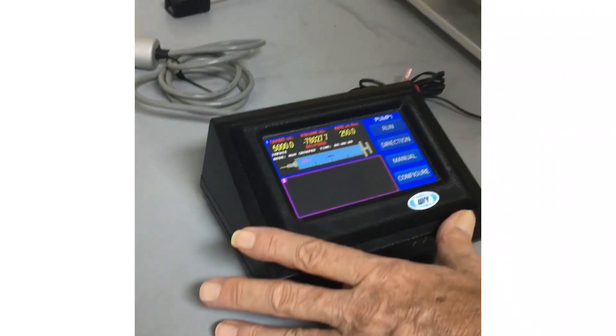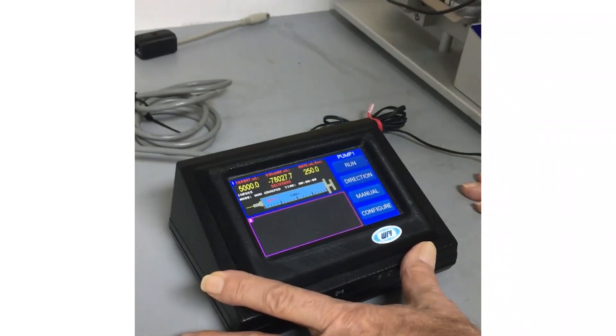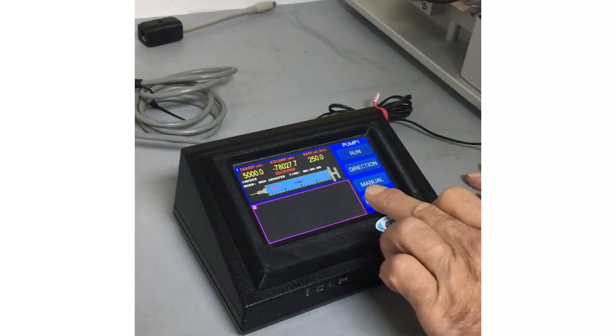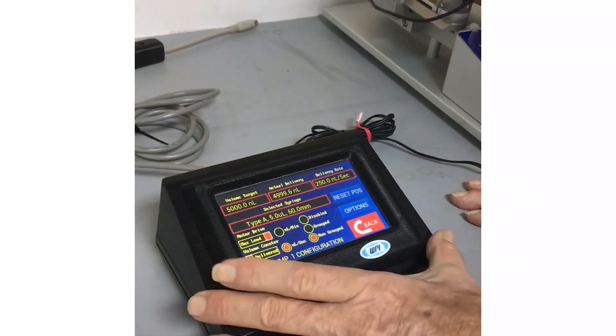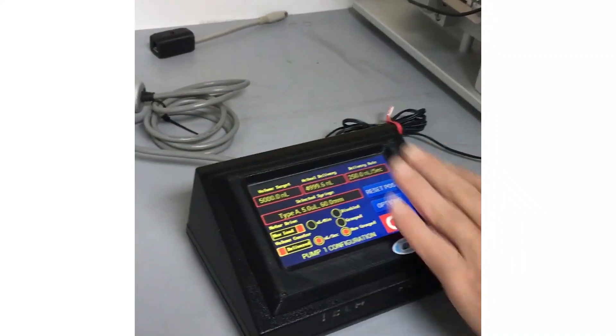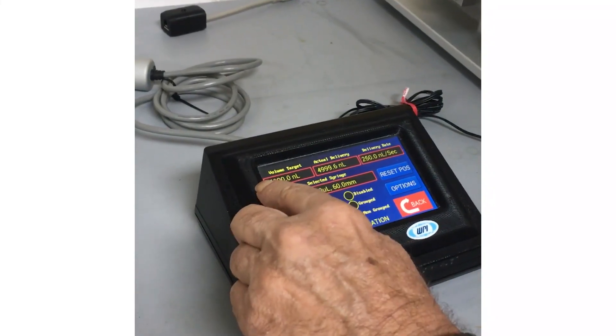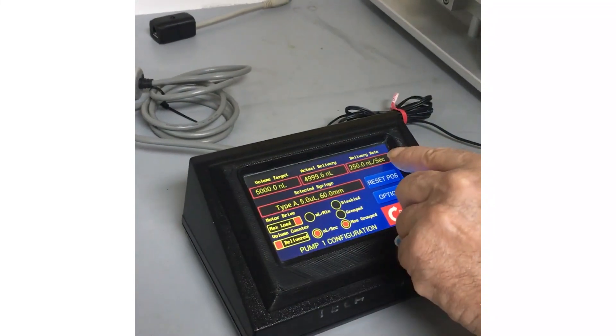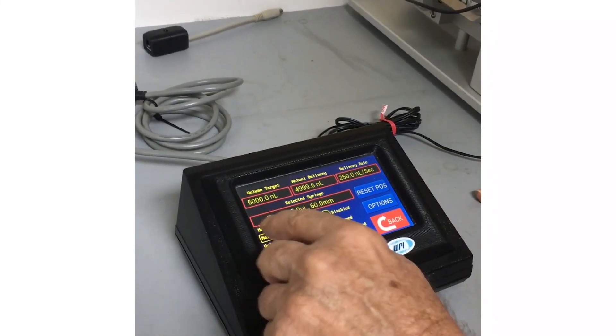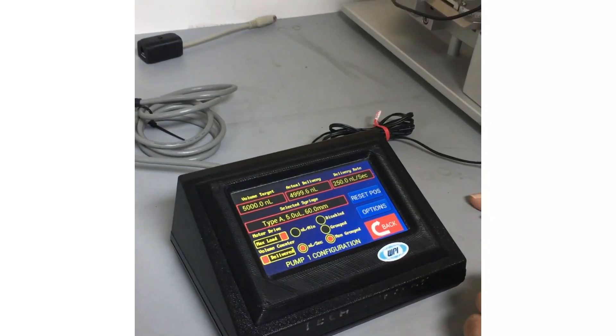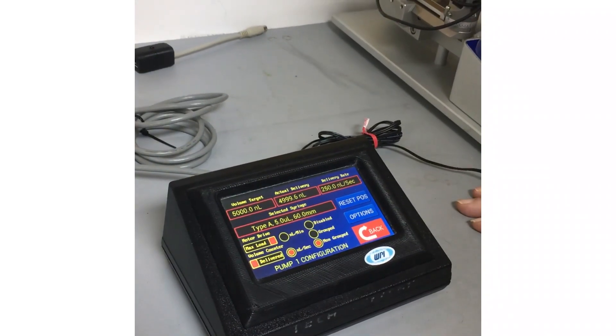The next thing you want to do is go to the configure page. This is where you're going to set up the syringe for how much volume you're going to inject, the delivery rate — ignore the center screen — but this one right here is the defined syringe. That's what we need to do: define which syringe we're going to use.